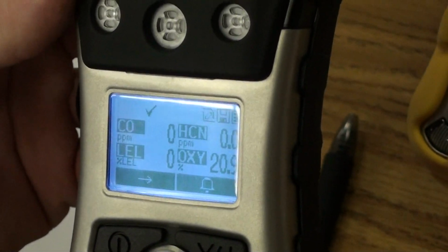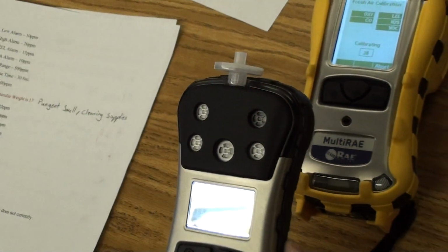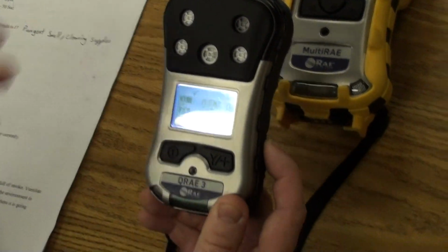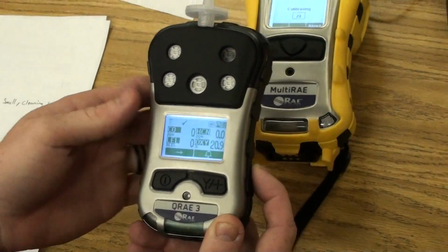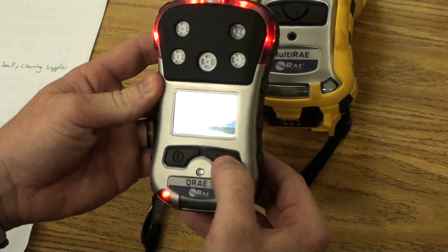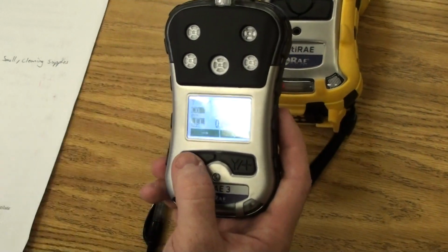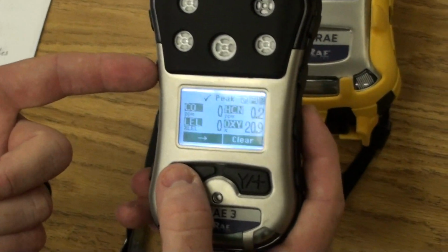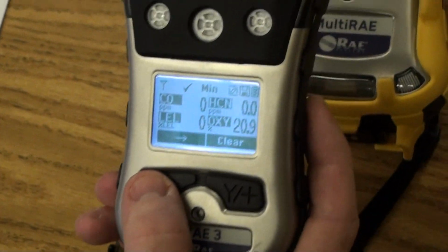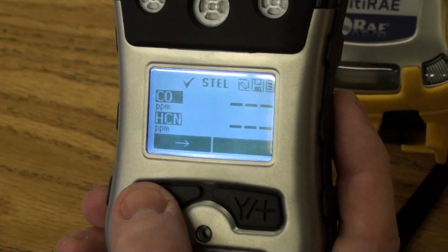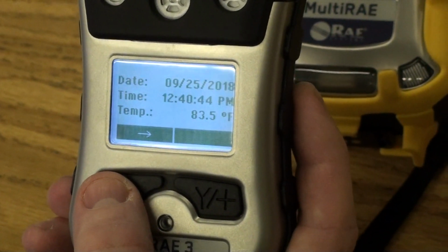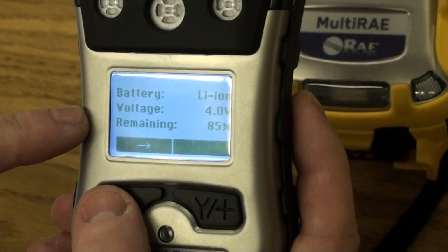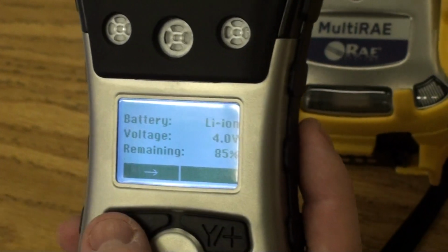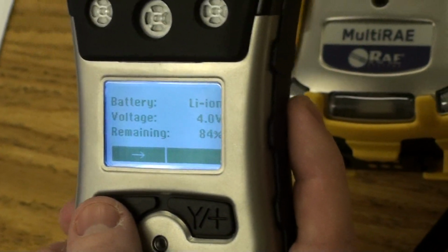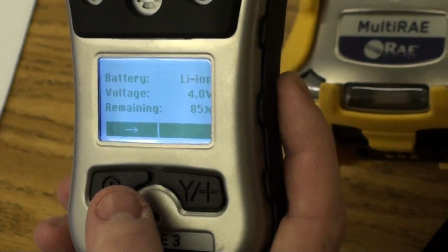Every morning after we start it up and do a fresh air calibration, we're going to put our finger over this filter on the top. That's to feel a suction coming out and to make sure that the alarm will sound. As long as you're on the home screen, there's a little bell there, and that's how you turn off the alarm. You can also scroll through, and it'll say peaks, minimums, short-term exposure limits, time-weighted average, say the temp and time of day, and here's where you can see the battery percentage. It says 85%. If it's ever 50% or lower, we're going to go ahead and recharge it for the day before we do anything else.